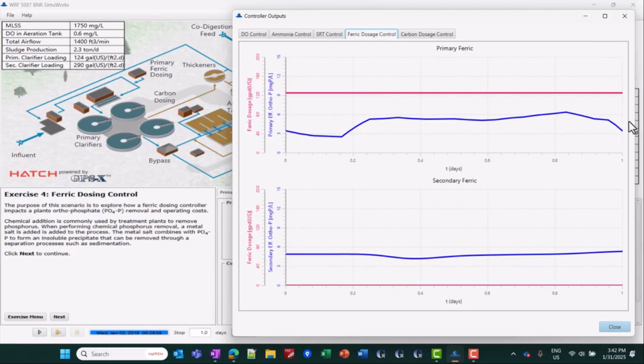Note that it goes up and down during the day. That's because we're dosing a constant mass, but the flow coming through this point in the plant goes up and down, so the actual concentration of ferric chloride changes. When there's more flow, there's less concentration, so it's not removing as much phosphorus, and the increased flow means more phosphorus coming through as well.